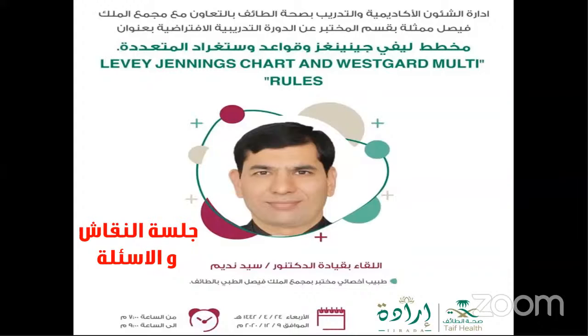The importance of Levey-Jennings charts is that it's an easy tool to look at, and you can gauge whether your system is processing properly or not. Just by a visual examination, you don't even need to look at the numbers. Just look at the screen, and if you see your controls within the 2 standard deviations, you can give a go-ahead green signal for processing the run of a batch or a random sample also. So Levey-Jennings charts provide you with a visual display. Even a technician who doesn't have much experience, when he opens the system and sees the Levey-Jennings chart and sees that the graph is within the 2 standard deviations, can judge that the system is working fine. So that's the advantage of the Levey-Jennings chart.